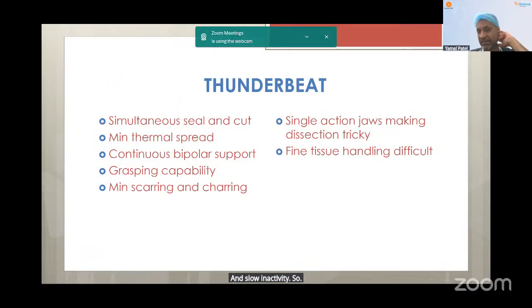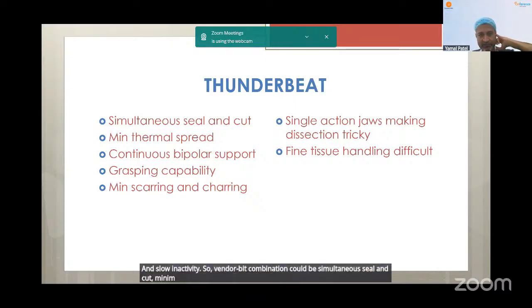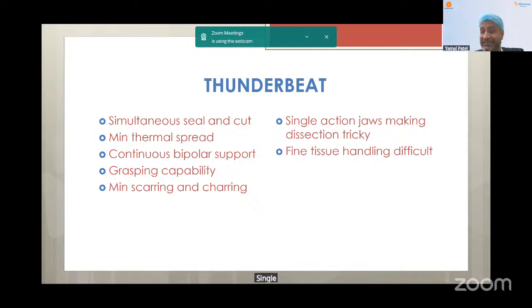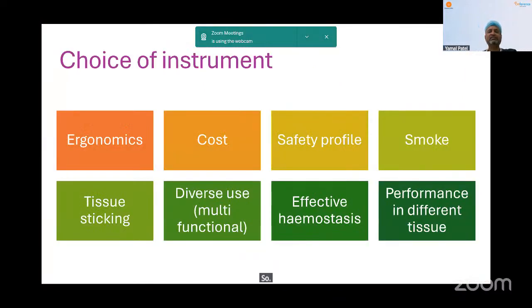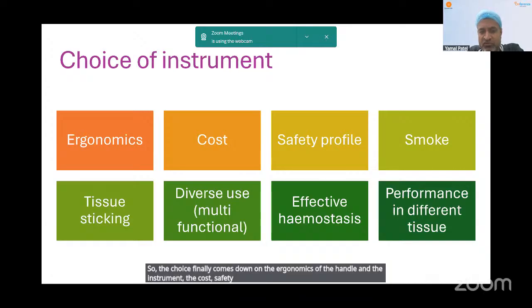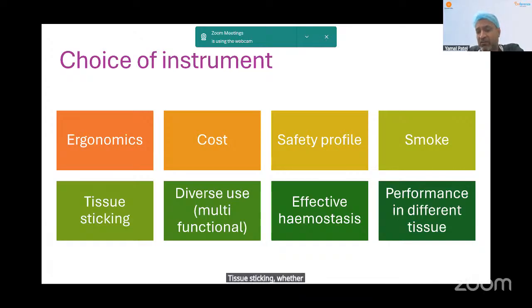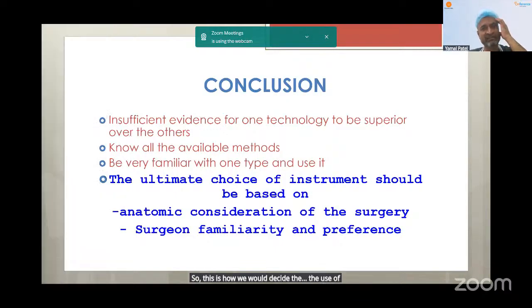So the Thunderbeat combination could offer simultaneous seal and cut, minimal thermal spread, continuous bipolar support with the cut, and the advantage of ultrasonic dissection. It has decent grasping capability and minimal scarring and charring, but the single action jaw makes dissection tricky, and fine tissue handling can be difficult. So the choice finally comes down to the ergonomics of the handle and the instrument, the cost, safety profiles, smoke produced, tissue sticking, whether it is multifunctional or not, effective hemostasis, and, in difficult situations, how its performance is. This is how we would decide on the use of ultrasonic versus advanced bipolar.